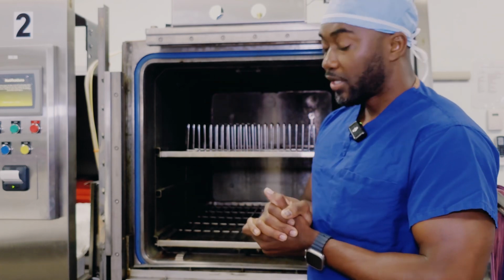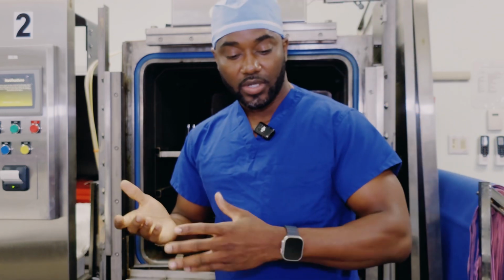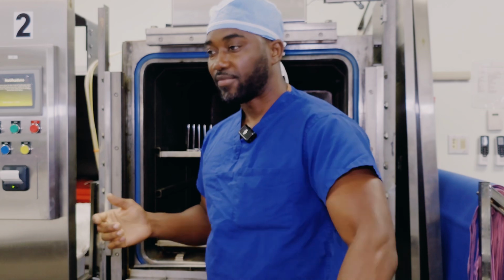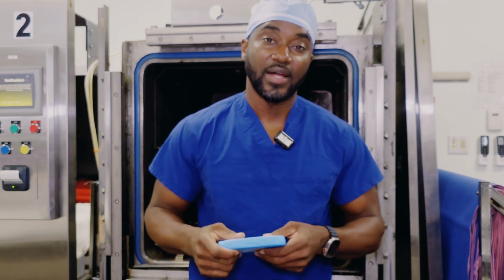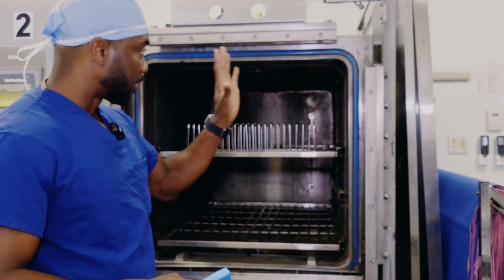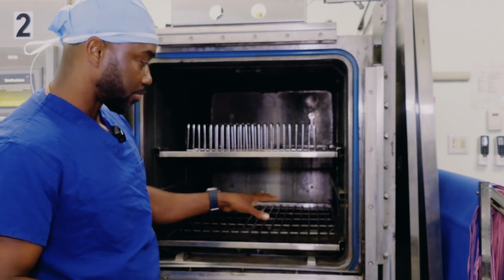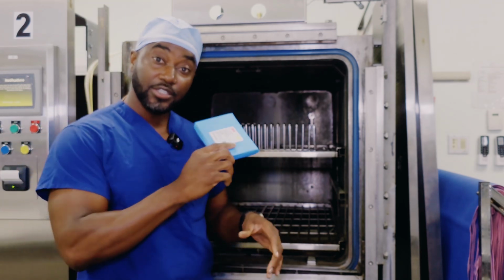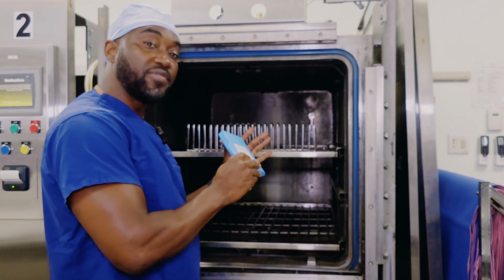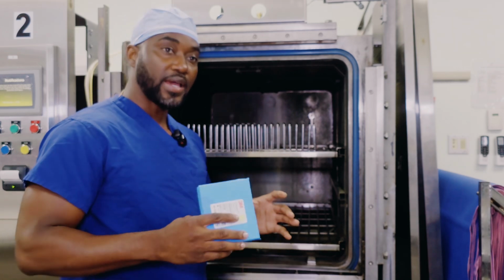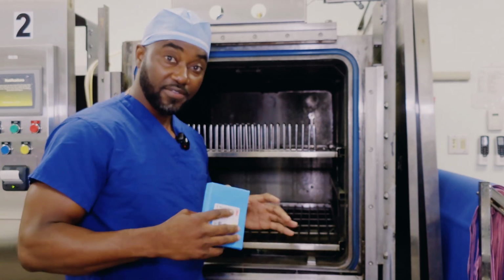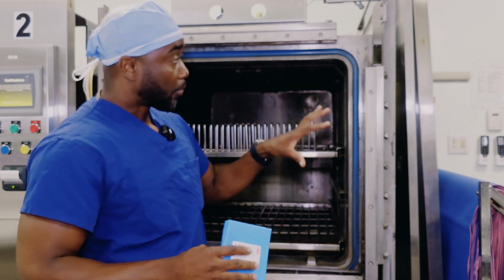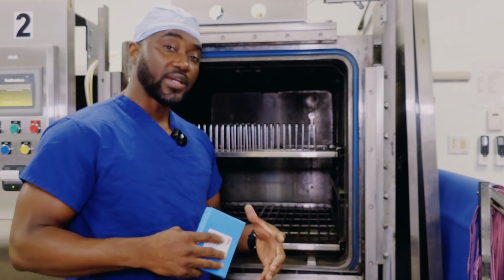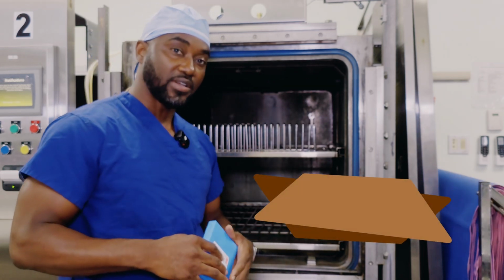Before we start our day, we have to run quality assurance tests on this autoclave. Once a week, as per our policy, we run our leak test on this chamber right here. This is the sterilization chamber. And in order for sterilization to occur in a pre-vacuum sterilizer, it has to happen with the absence of air in the sterilizer. For pre-vacuum sterilizers, the way that air is displaced from the sterilizer is using vacuum pumps.